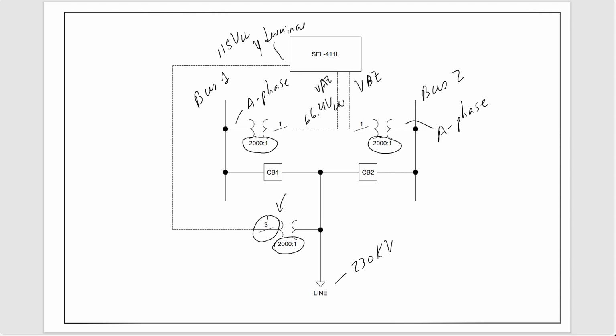Now, let me actually jump into a blackboard, and what I want to show you over here is that, again, what we're doing with this sync check element is we're making sure that the phase angle, magnitude, and frequency on both sides of each breaker are within a specified range prior to closing the breaker.